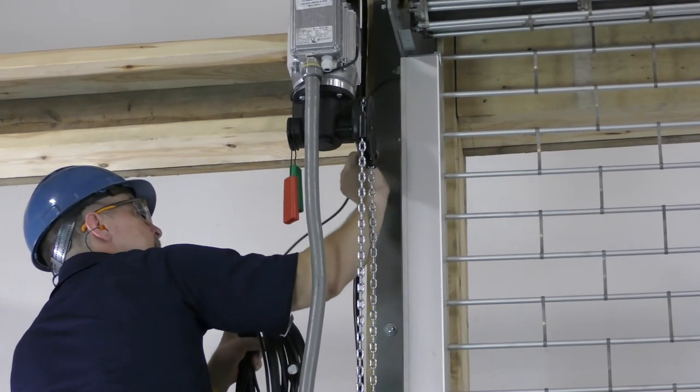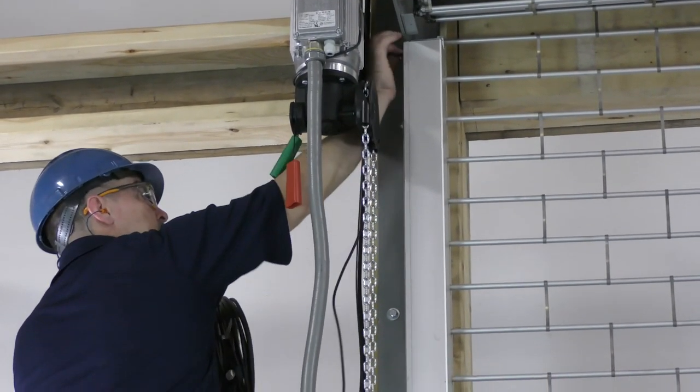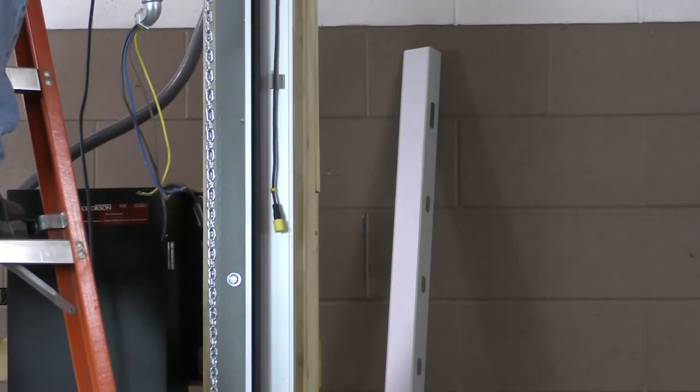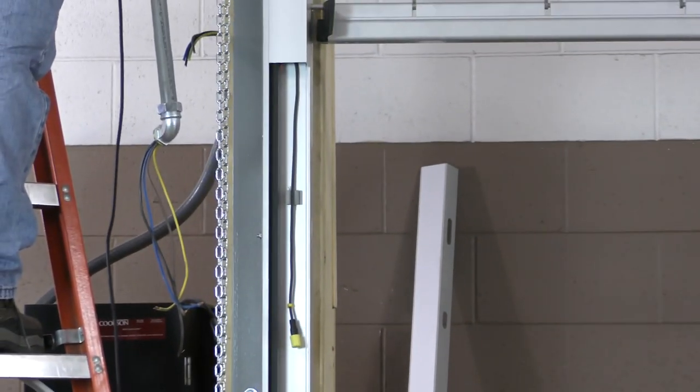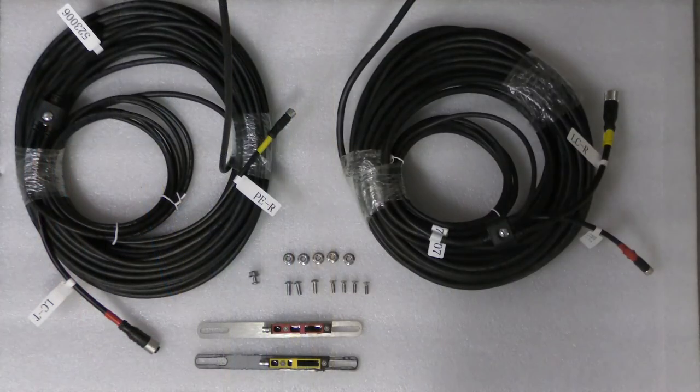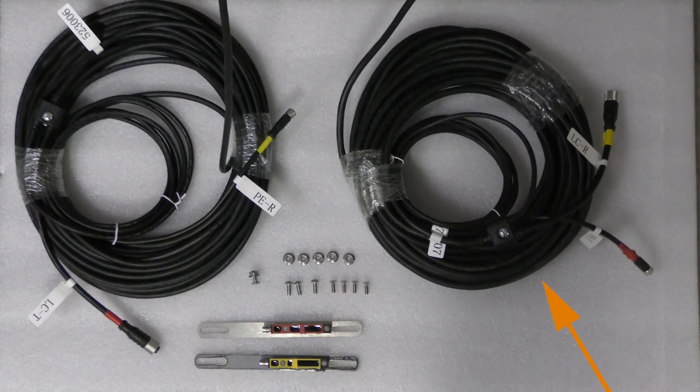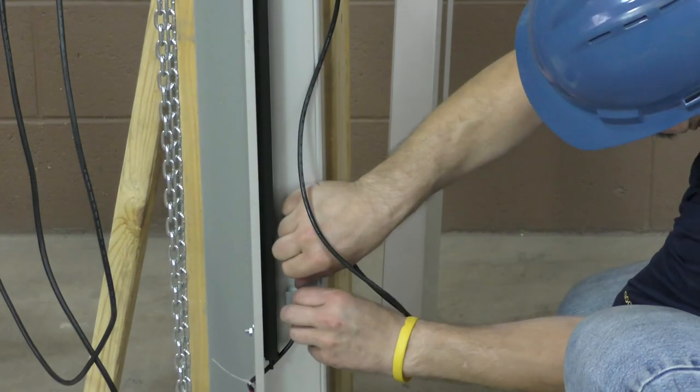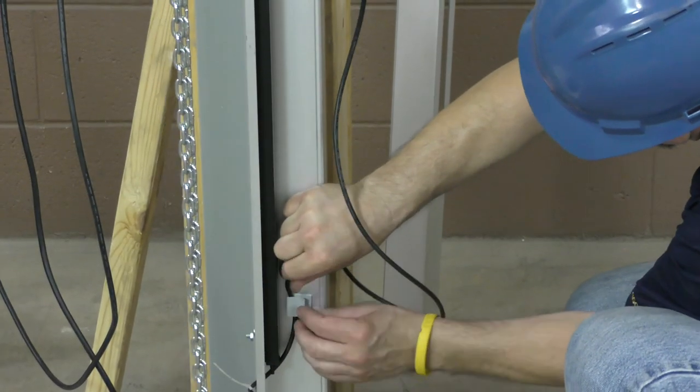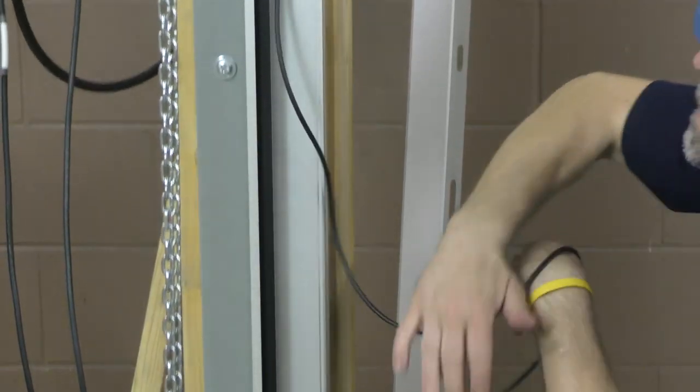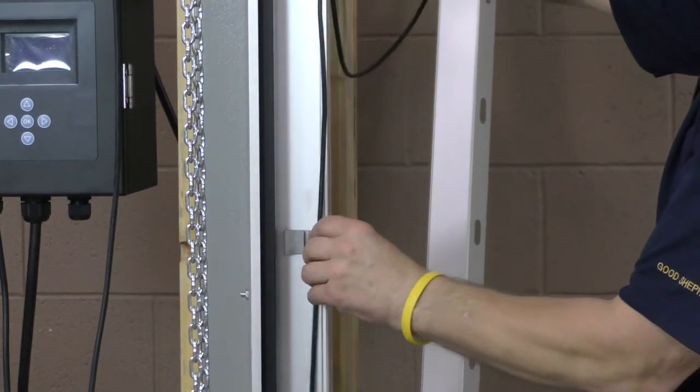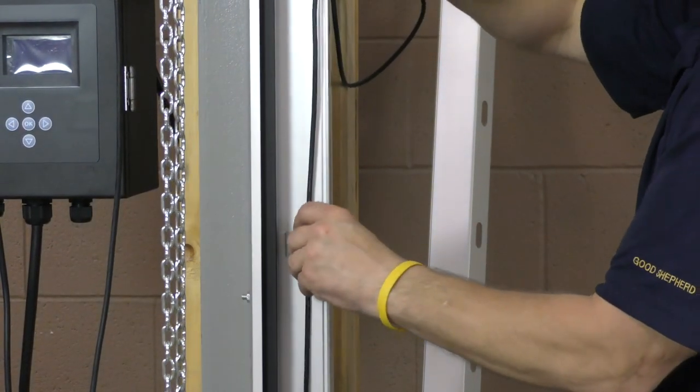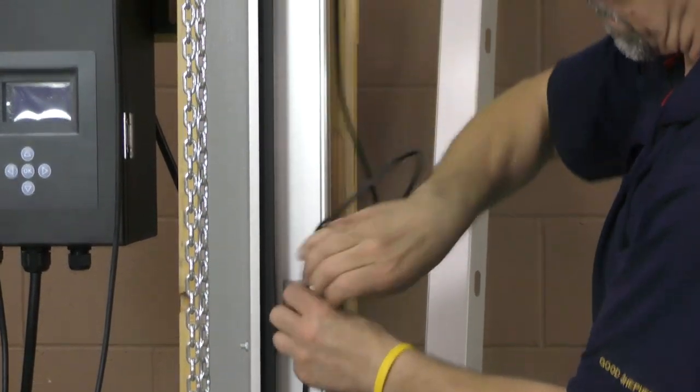Once the photo eyes are secured to the guides, route the plug and play connectors from the control panel to each side of the door. Make sure the shorter cable runs to the operator side and the longer cable runs to the adjuster side. Use the access holes at the top of the guide to run the wiring through, using the pre-installed clips to keep the wiring in place.